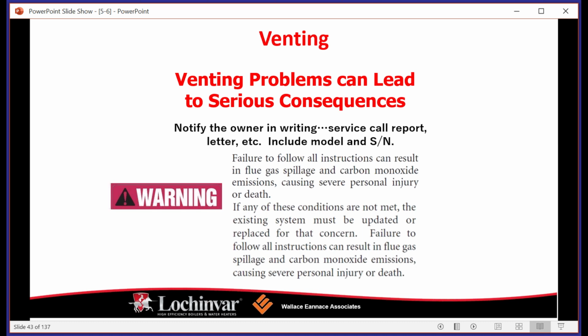So it's on you to make sure that this is done correctly as a contractor. If you're a GC, you need to make sure that venting is taken very seriously, because there is a potential for a life safety problem. If carbon monoxide goes into a living space over a period of time and people are exposed to it, it can be fatal. Everybody sees it every winter. Somebody tries to vent improperly, or they light a combustion appliance inside their house because they think they can save money on their fuel bill, and they end up killing a whole bunch of folks, which obviously you don't want to be responsible for.